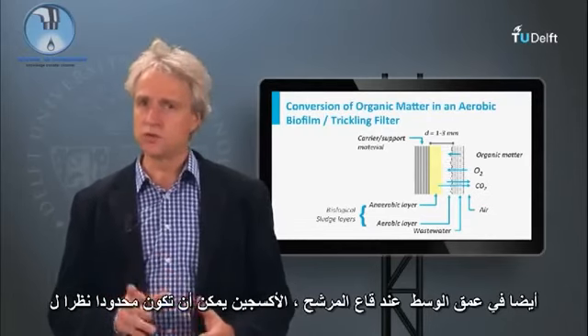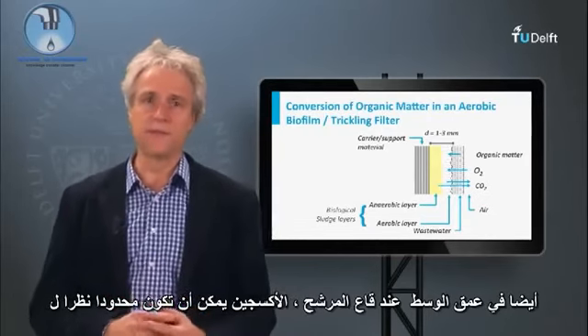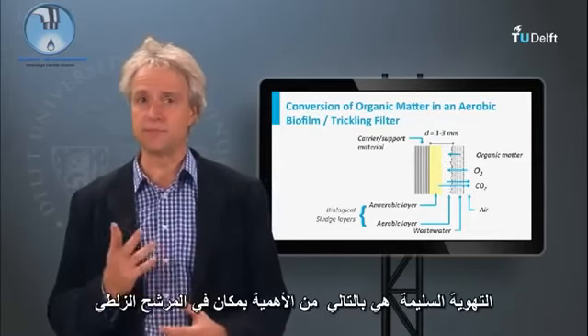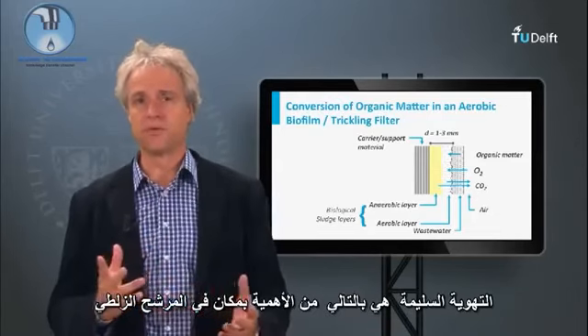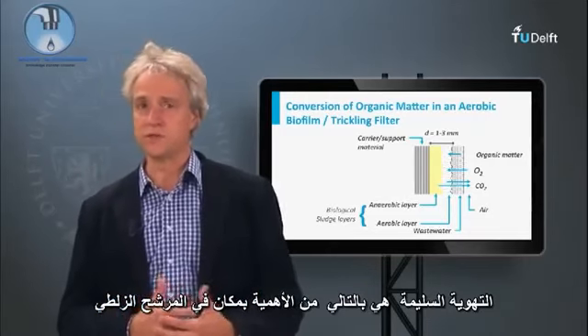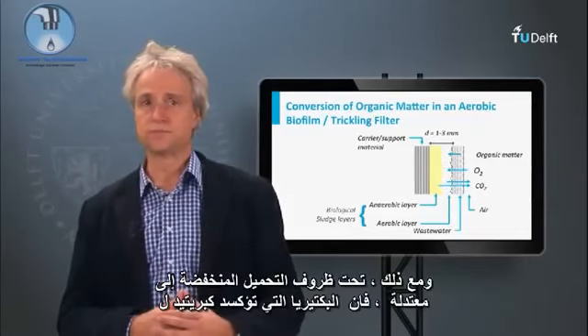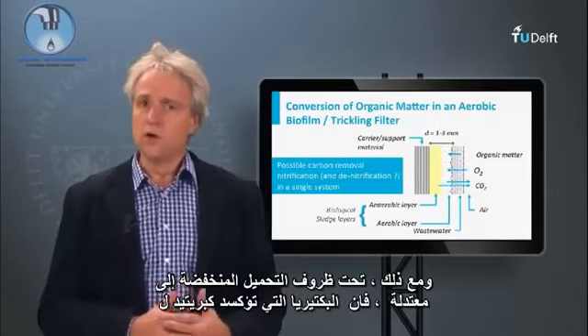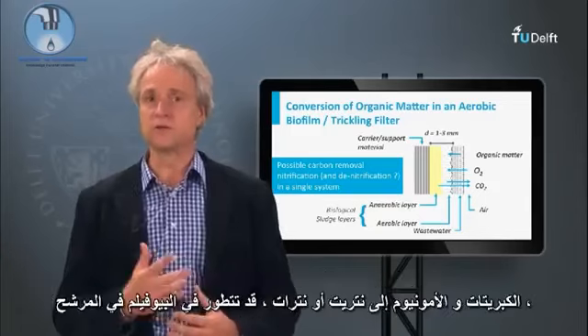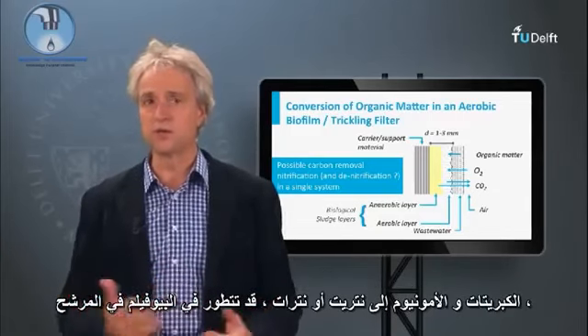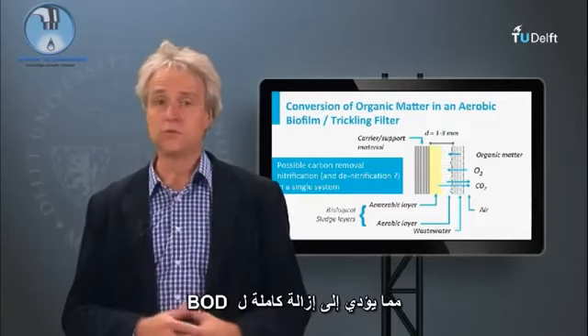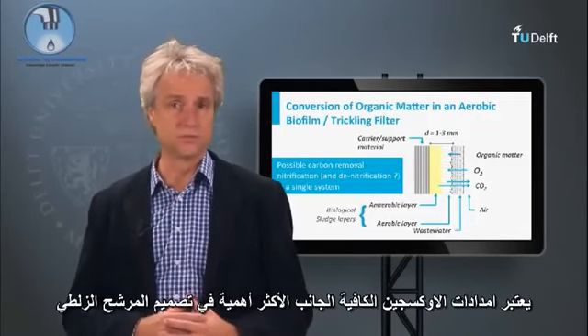Also deeper in the bed towards the filter floor, oxygen can be limited owing to the high biological activity at the top. Proper venting, or air supply, is therefore of utmost importance in the trickling filter. However, under low to moderate loading conditions, also the bacteria that oxidize sulfites to sulfate and ammonium to nitrite or nitrate may develop in the biofilms of the filter, leading to full BOD removal.